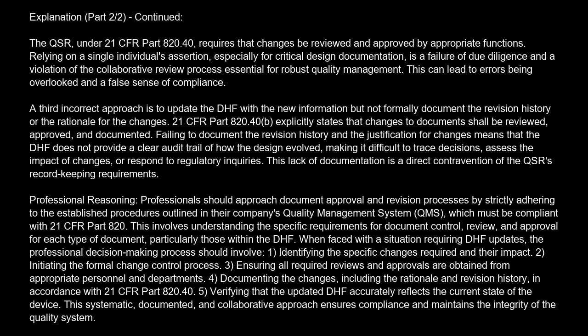2. Initiating the formal change control process. 3. Ensuring all required reviews and approvals are obtained from appropriate personnel and departments. 4. Documenting the changes, including the rationale and revision history, in accordance with 21 CFR Part 820.40. 5. Verifying that the updated DHF accurately reflects the current state of the device. This systematic, documented, and collaborative approach ensures compliance and maintains the integrity of the quality system.